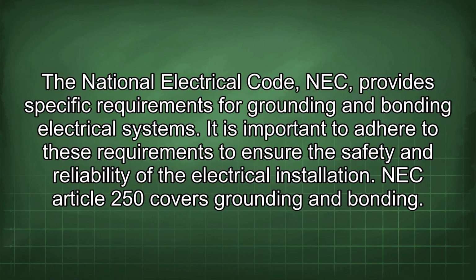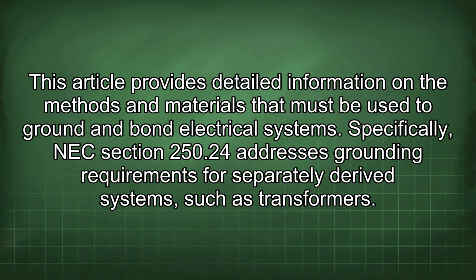The National Electrical Code (NEC) provides specific requirements for grounding and bonding electrical systems. It is important to adhere to these requirements to ensure the safety and reliability of the electrical installation. NEC Article 250 covers grounding and bonding. This article provides detailed information on the methods and materials that must be used to ground and bond electrical systems. Specifically, NEC Section 250.24 addresses grounding requirements for separately derived systems such as transformers.